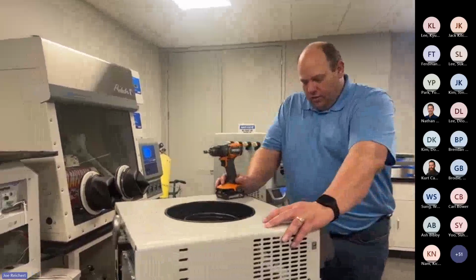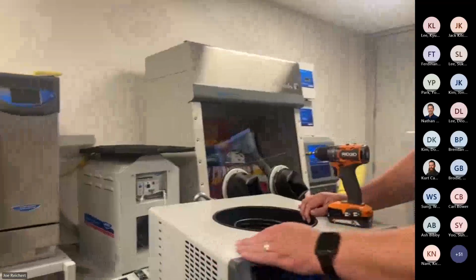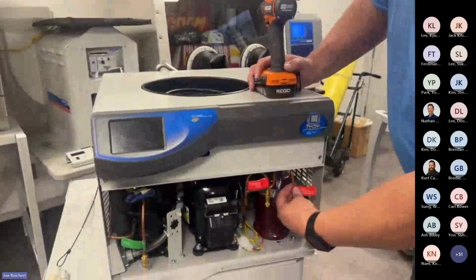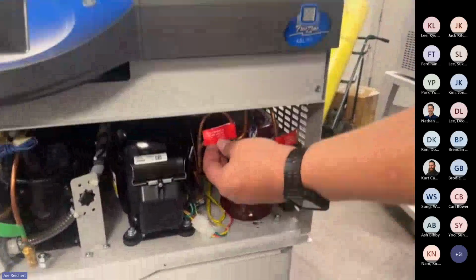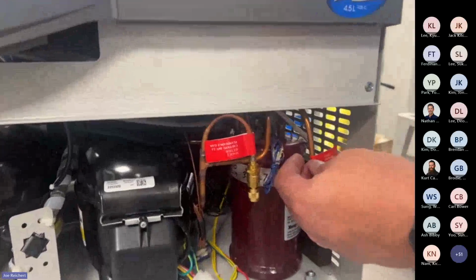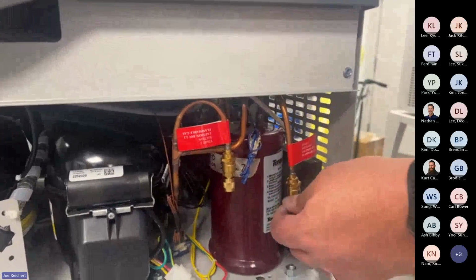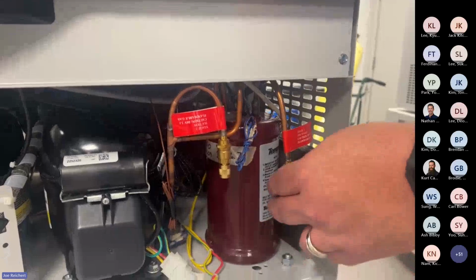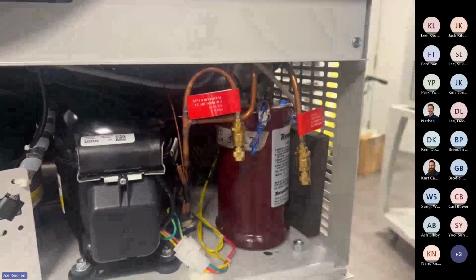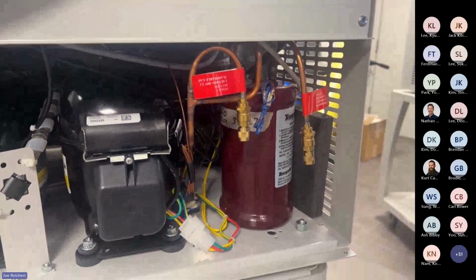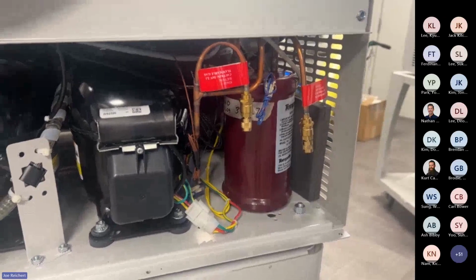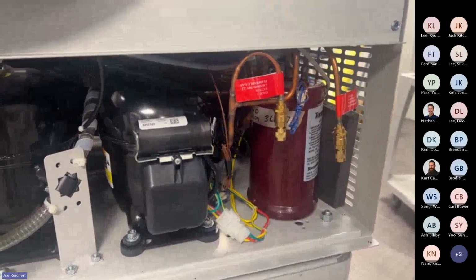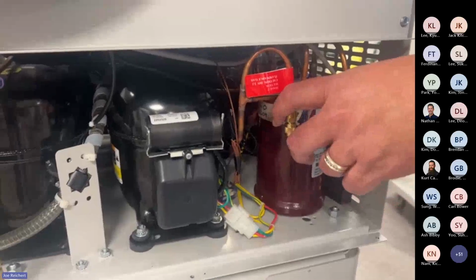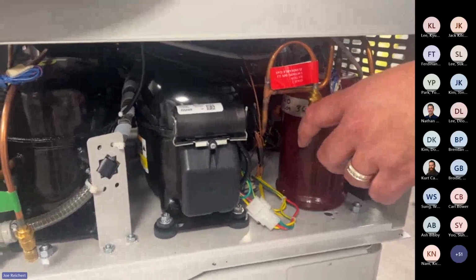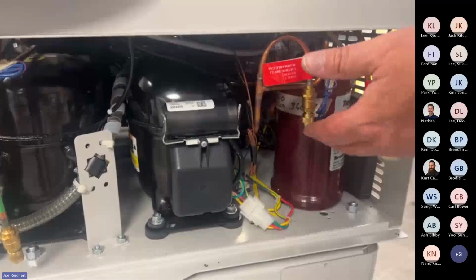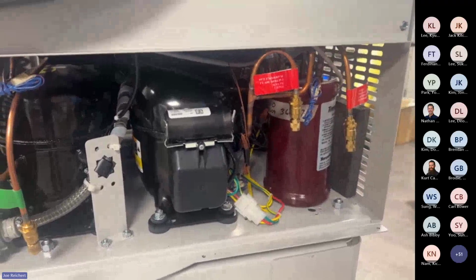So now on the front of the machine is where we have all of our process valves. They're all labeled. Your stage 2, you have your suction, you also have a discharge. I don't have a recording of what the discharge pressures are. We just do mostly suction on everything we use. Even when we're building the units, we use the suction pressure. But there is a discharge valve. The reason why we have both of them on a minus 105 is we charge it from both sides, and it's faster for charging it that way.